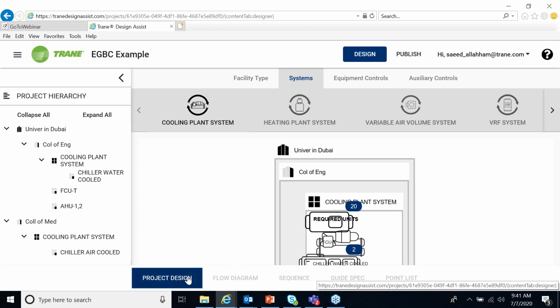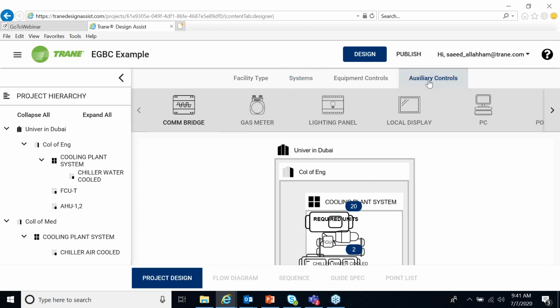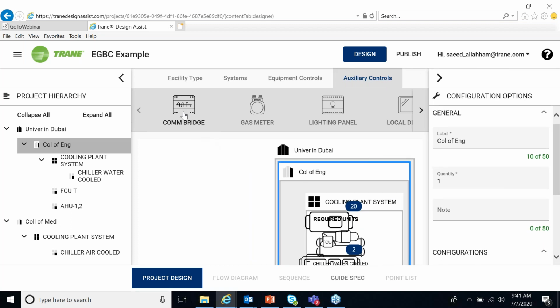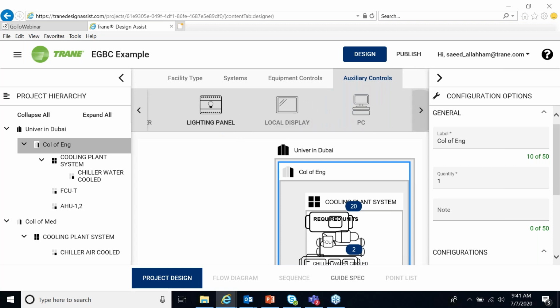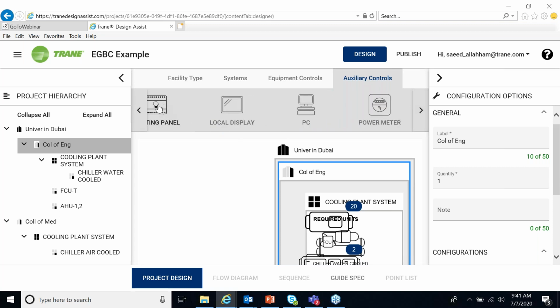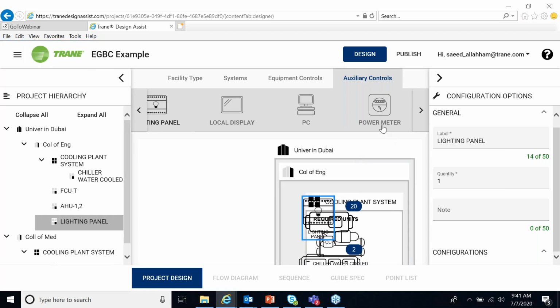I think with that tour, we went through most of it. There are also some auxiliary controls that you can add to the BMS system or for the control system. You can add, for example, gas meters. You can add lighting panels if you want, for example, to the building. If you have a lighting panel, you can drag it and add it to the system. Or if you have power meters, you can also add them to the systems.